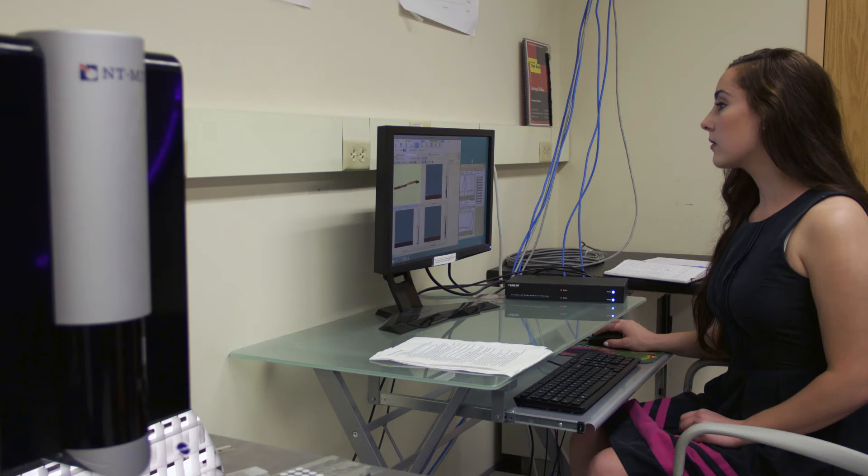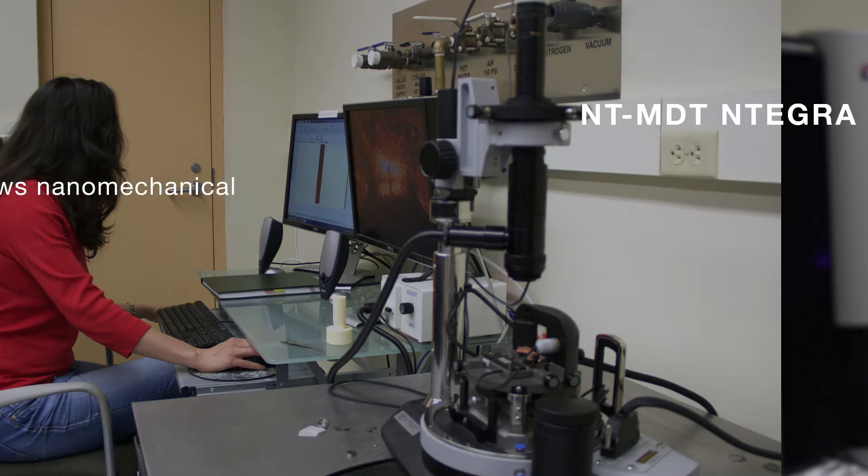The Solver Next additionally has a hybrid mode system that allows us to take nano-mechanical measurements of the sample, things like surface deformation and surface adhesion, on the scale of the AFM tip. The NTEGRA, on the other hand, is a modular system, so we can add and subtract pieces to measure the things we want, like a sample submerged in liquid or very high-resolution scans.